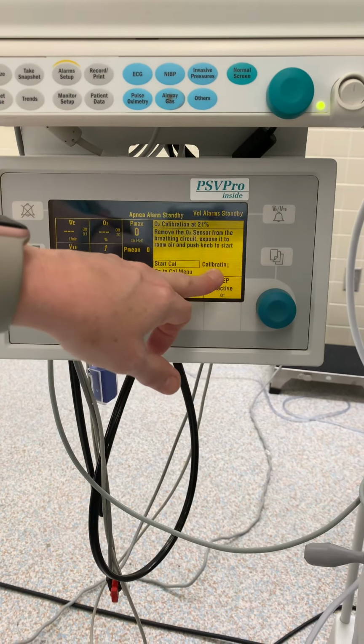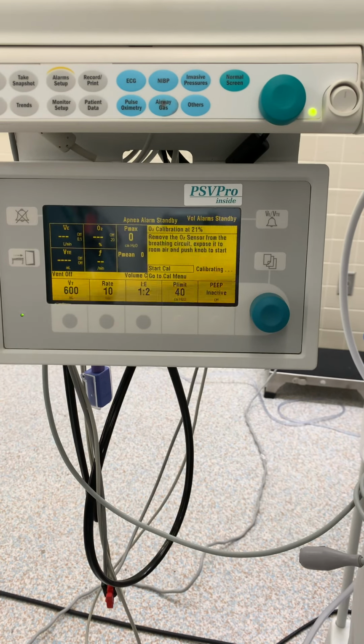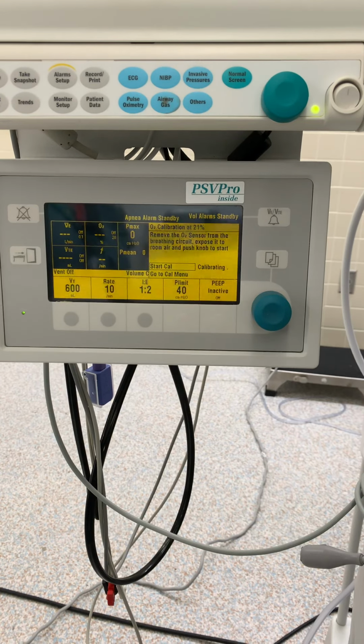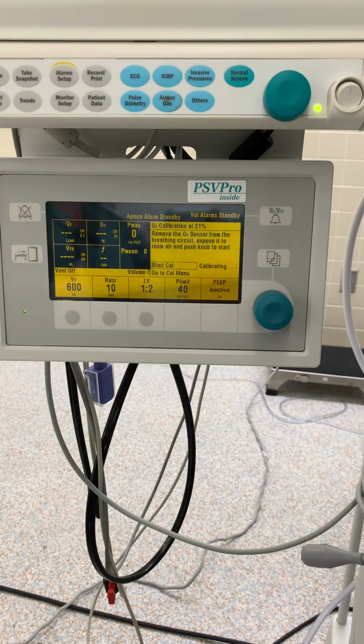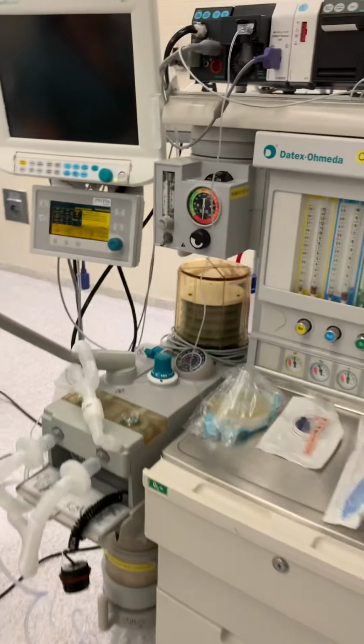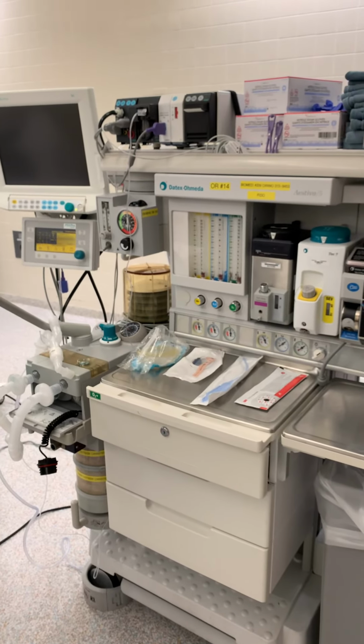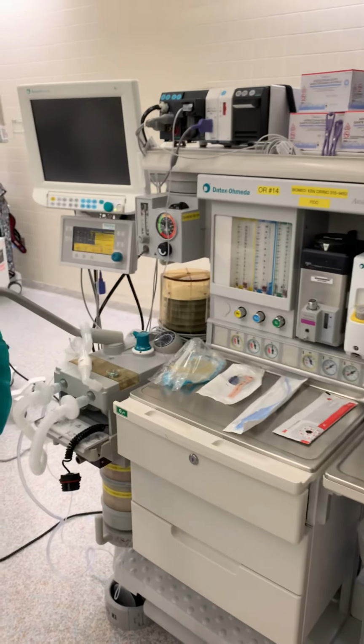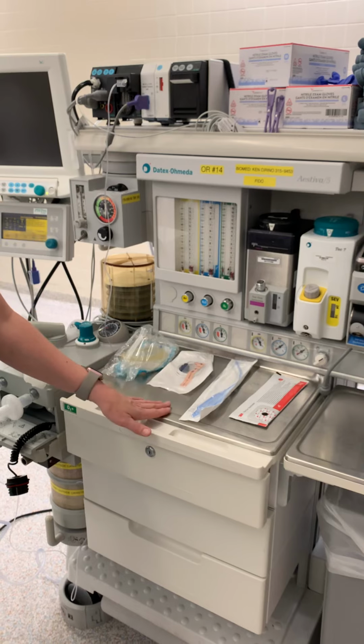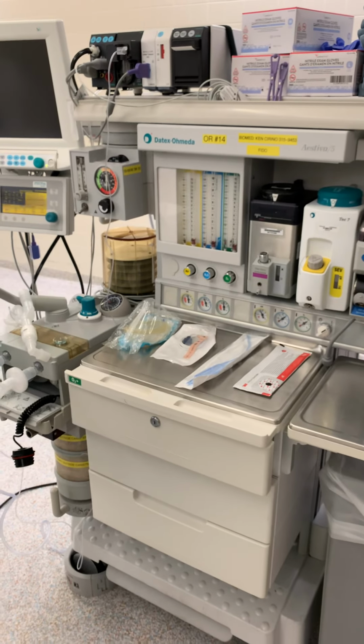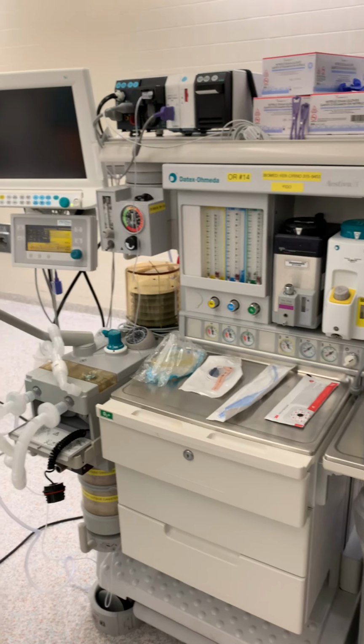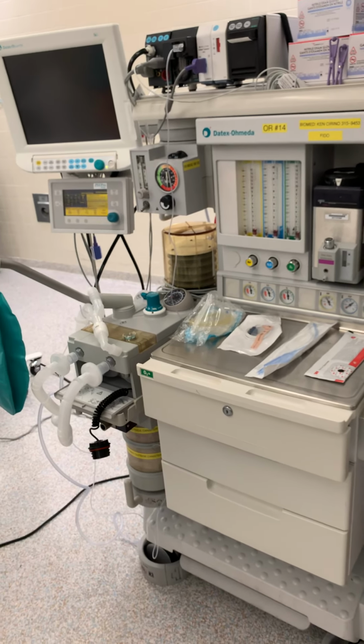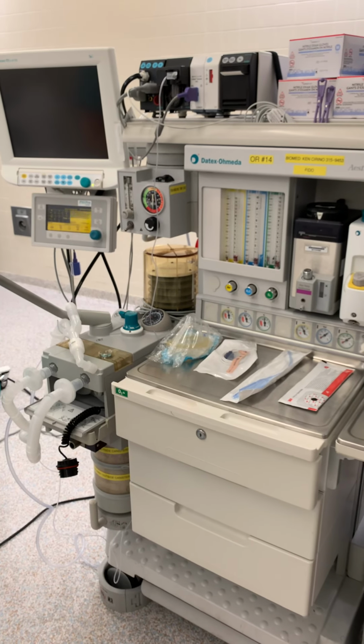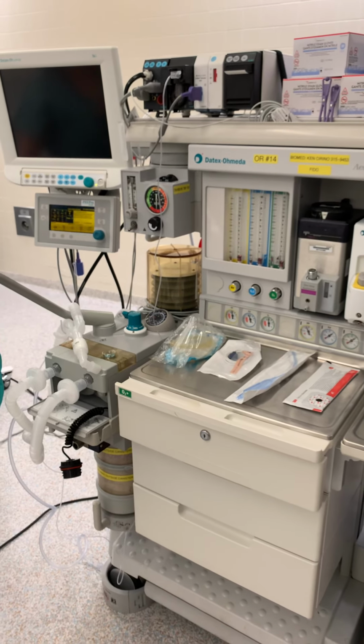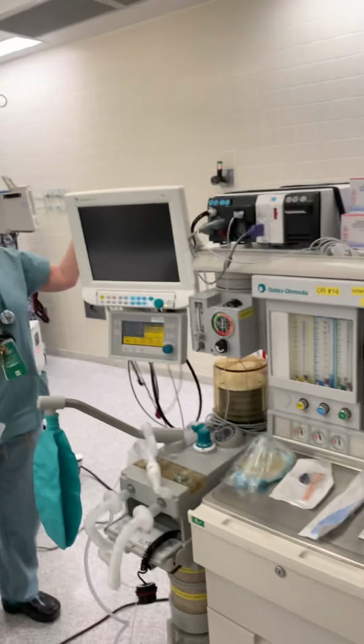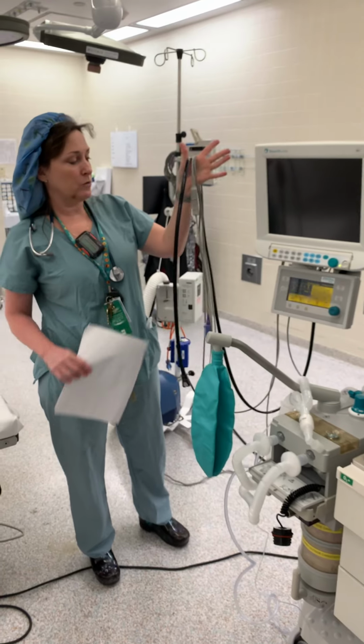And you know that you've started calibrating when the machine starts to say calibrating. Now this can take a few minutes to calibrate. So this would be a time to maybe lay out some of your anesthesia equipment, or just make sure that you've got a mask, a pulse ox probe, a suction device, some EKG pads. And again, it'll give you the opportunity in this checkout to do that. When you get to the point you can multitask, you can at this point make sure that you've got your cables for monitoring, your blood pressure cable, EKG, pulse ox, while you're waiting.